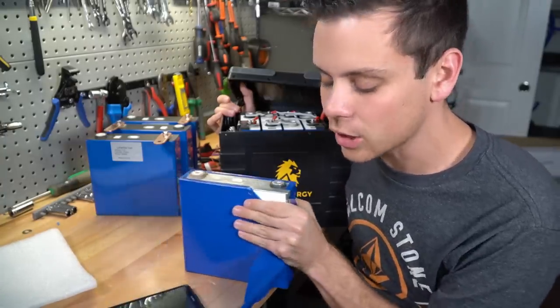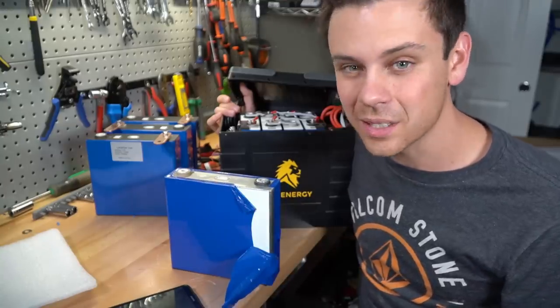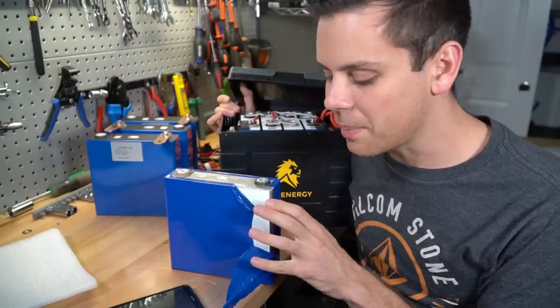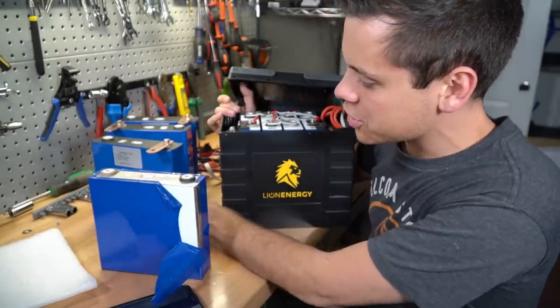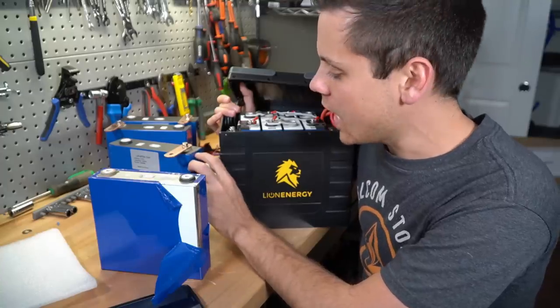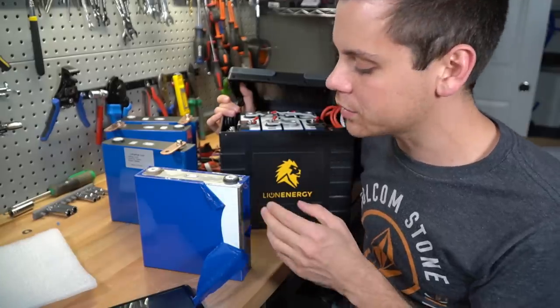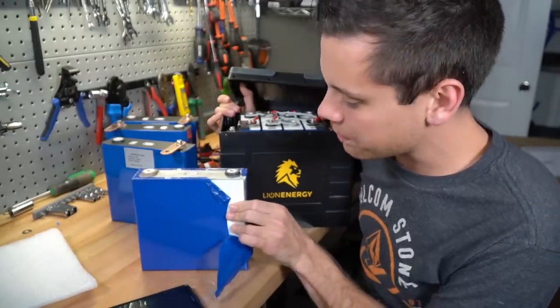And let's say we use a lower capacity cell in like a 48 volt lithium iron phosphate. That's going to be 16 cell battery bank. And this will reduce the capacity of the whole battery bank. Because I have a hunch that these other ones are just fine given their voltage at that low state of charge. But this one is the lowest common denominator and will determine the capacity for the entire bank. So yeah, that's bad.